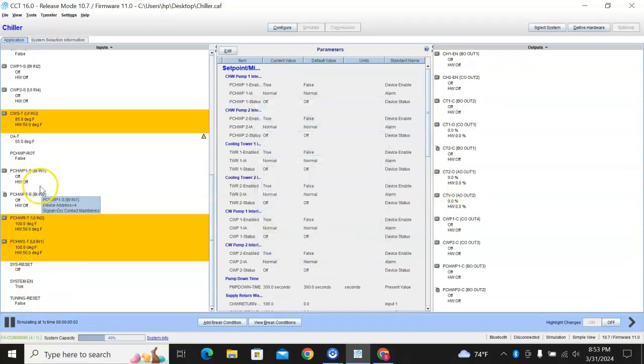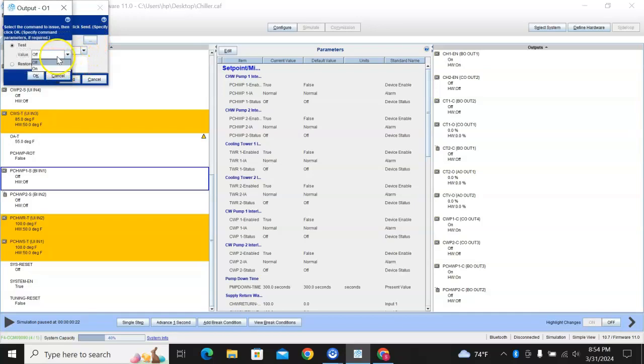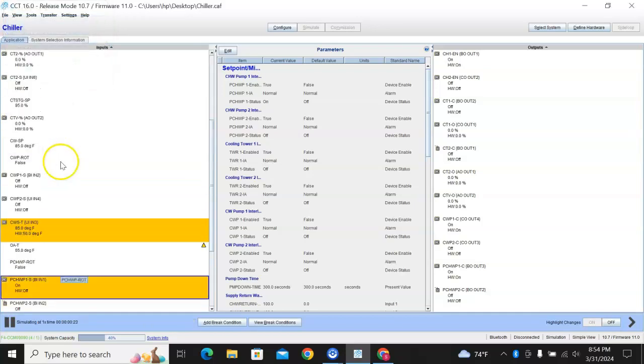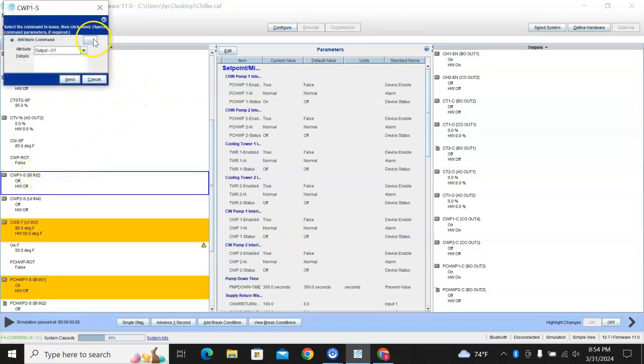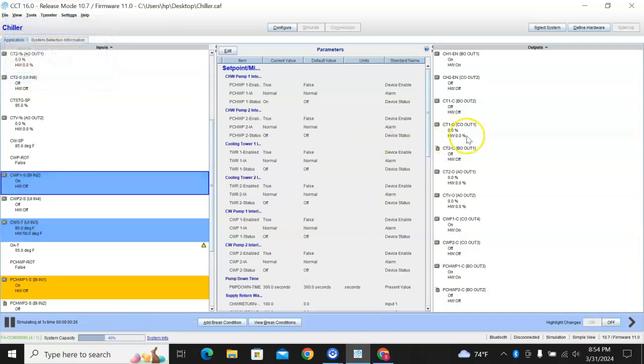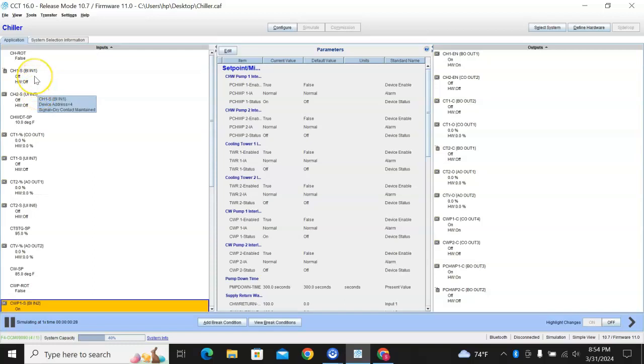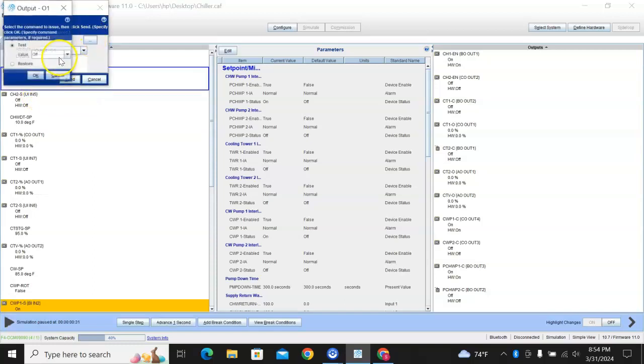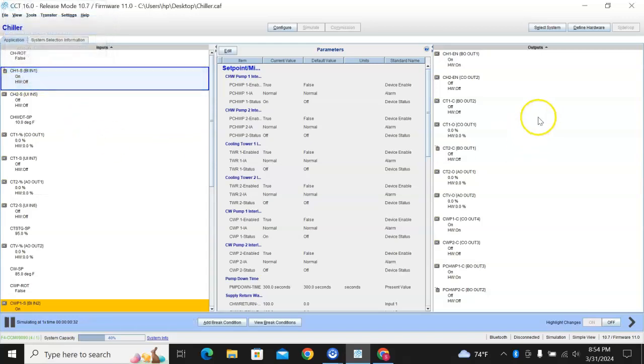Now I already know primary pumps are going to turn on first, right? So I can go ahead and start getting ready for that. I'm waiting for a primary pump to turn on here. And the condenser water pump. Both of those should turn on at the same time, so I'm going to try to be fast. Turn mine on at the same time. That way they don't go into alarm. And then condenser water pump. And then chiller. There we go. That was fast enough that we don't get alarms.